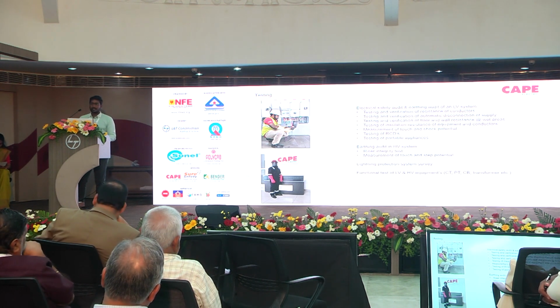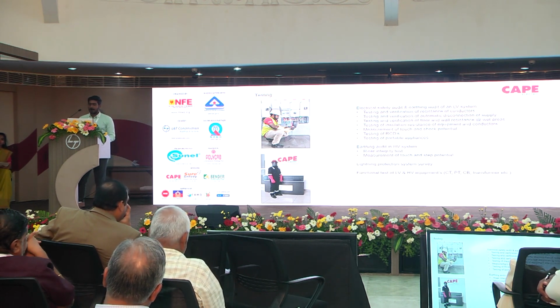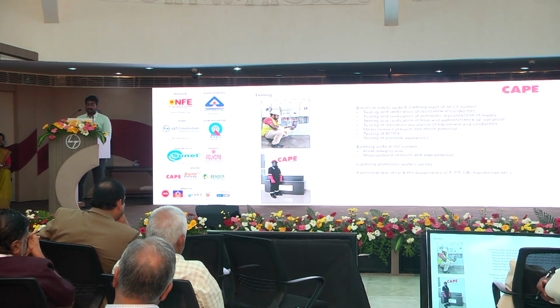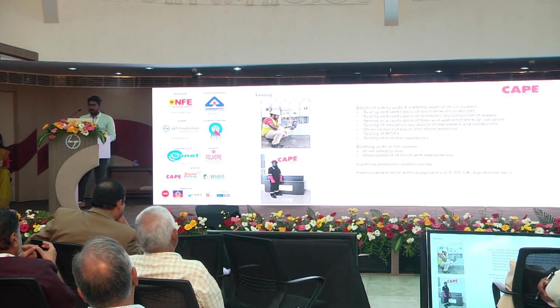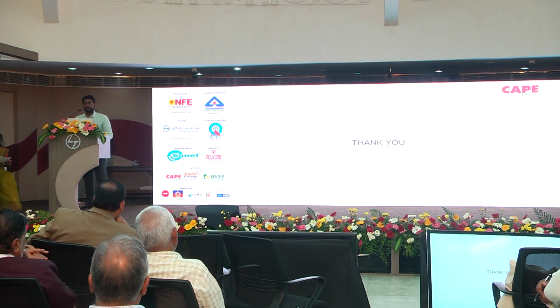So we are doing testing and verification of resistance of conductors and automatic disconnection of the supply, floor and wall resistance at wet areas, and the resistance of the equipment and conductor, which is testing of insulation resistance of equipment and conductors, and measurement of touch and shock potential. And we are also doing testing of RCDs and portable appliances. Earthing audit in HV systems will include an indicative test for the complete HV area and measurement of touch and step potential. Apart from this, a lightning protection system survey will also be done, and functional tests of LV and HV equipment with respect to CT, potential transformers, and CB transformers, etc. So thank you. This is an overview of our product.